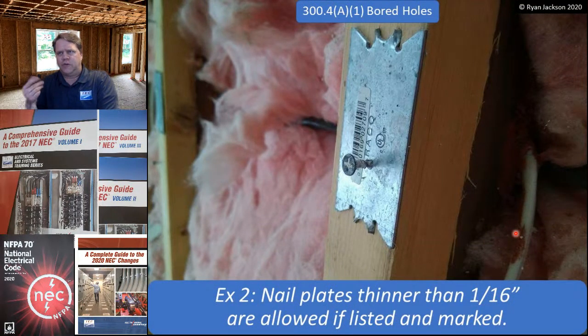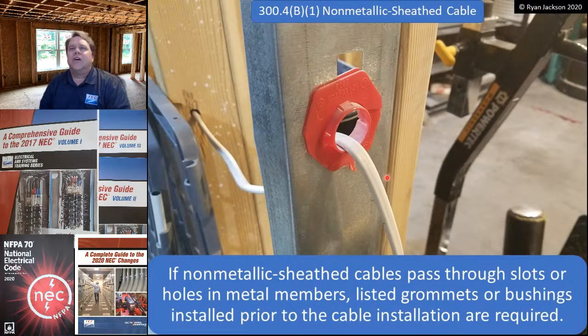There's two exceptions. The first exception doesn't apply to NM cable, and that's why I'm not going to cover it. But it says, if you're using conduit, EMT, you don't need nail plates. The next exception, nail plates that are thinner than 1/16 inch are allowed if they're listed and marked. Well, there is our listing, and as you can see, you cannot possibly penetrate a listed nail plate with a drywall screw. So that's the idea anyway. You know, I think the drywaller is like, oh really? Well, hold my beer.